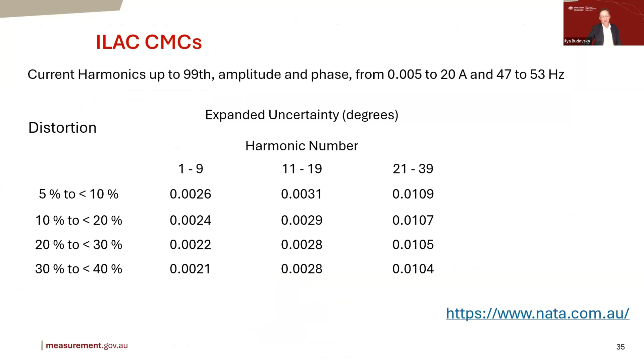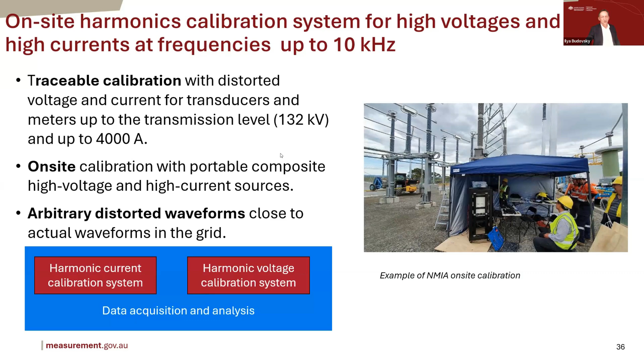Finally, just to end on a high note, I'd like to go to high voltage, where it's also becoming really important to measure harmonics, and particularly to measure power with composite signals that contain the fundamental plus an arbitrary content of high voltage and high current harmonics up to 10 kilohertz. The harmonics are really beginning to penetrate not only distribution networks but also transmission networks, and knowing their propagation and mitigating it requires measurement. So that's what we have developed to support this process.